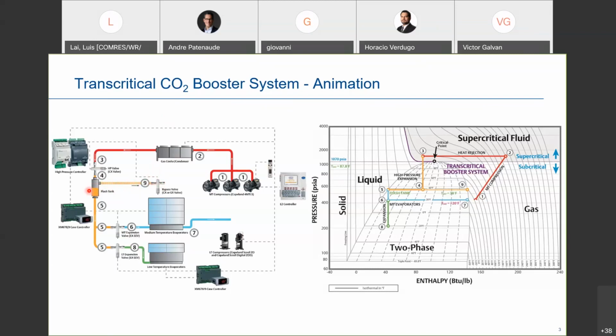If the pressure is constant, the saturated temperature will be constant, and then your liquid quality going to all your valves will be constant. So this valve is continuously modulating in order to maintain pressure. But when it does that, it's bypassing that load into the low side. So when we take a look over here between 4 and 9, on the left, 4 and 9 is bypass gas. When you go to the enthalpy diagram, 4 to 9, you've got vapor there. When you're injecting vapor from point 9, you're dropping its pressure down to a medium temp saturated point.